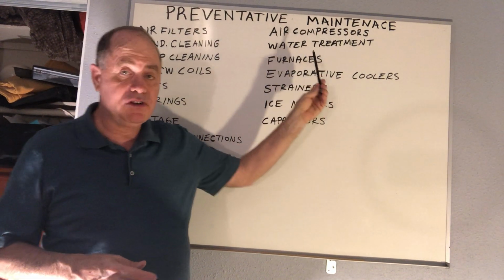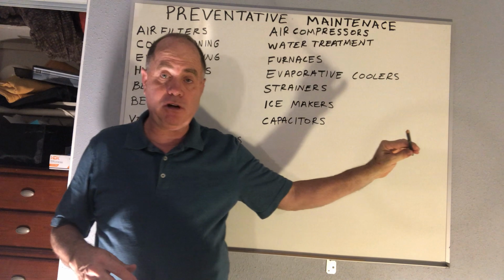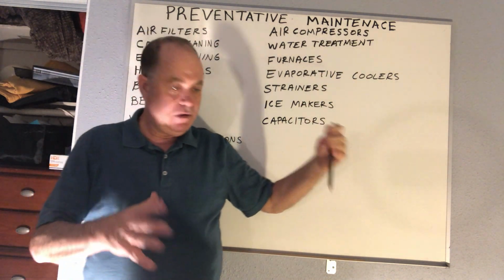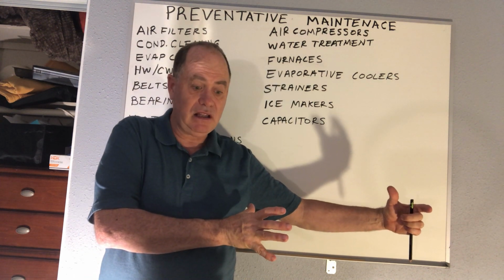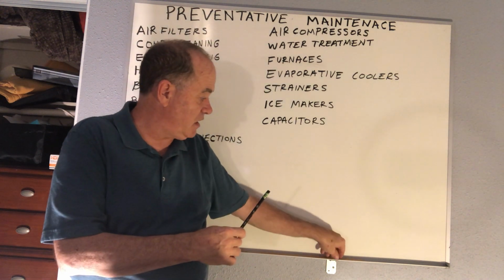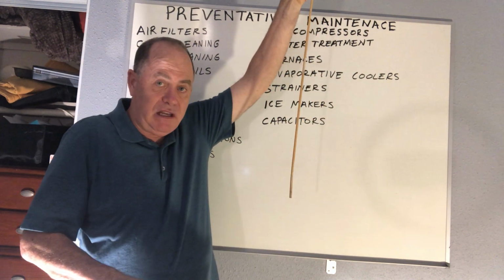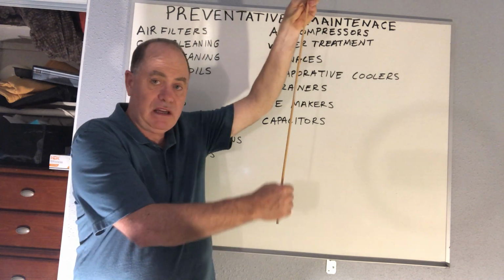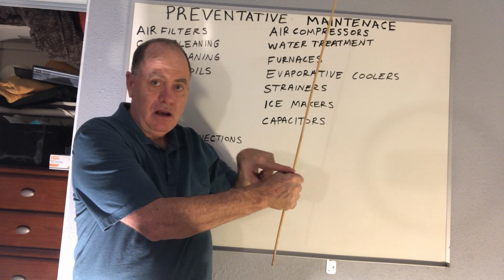Now, you also need to make sure you're pumping chemical on a regular basis, scale inhibitor, algicide. For the scale inhibitor, they have a polymer test. But if you have a reservoir, a big cylinder of scale inhibitor, you can take something like a yardstick, something like this but flat, where you can write on it, and then you can put it down in the container until it hits the liquid level, and then you could put a line with a date on that.